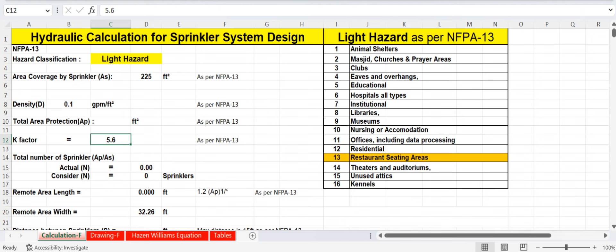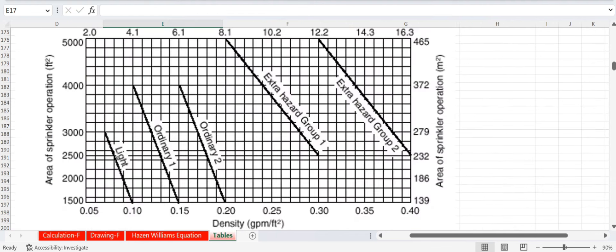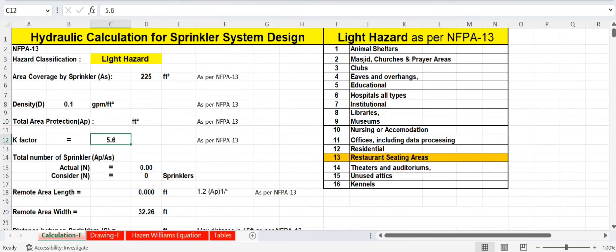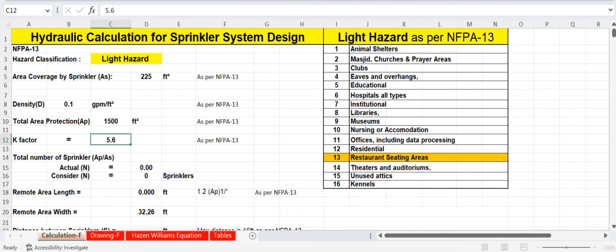Next is total area protection. From the table, for light hazard the area of sprinkler operation is 1500 square feet. Enter 1500 square feet as the total area protection for the sprinkler system.